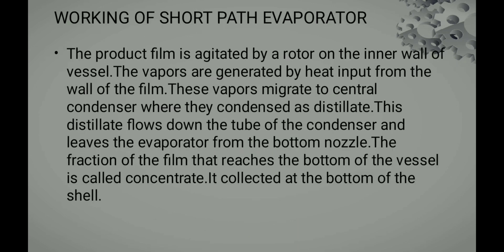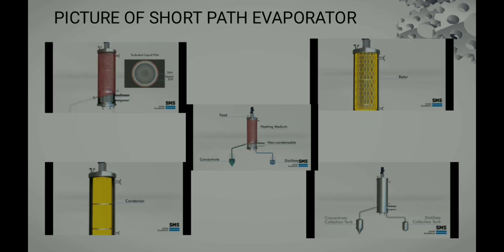Let us see the working of the short path evaporator. The product film is agitated by a rotator on the inner wall of the vessel. The vapor generated by heat input from the wall of the film migrates to the center condenser where it condenses as a distillate. This distillate falls down to the tube of the condenser and leaves the evaporator from the bottom nozzle. The fraction of the film that reaches the bottom of the vessel is called the concentrate, and it is collected at the bottom of the shell.